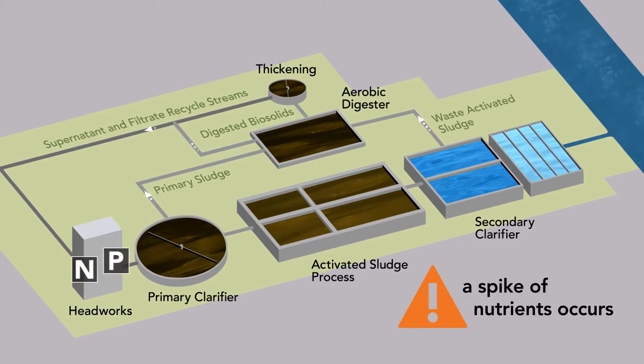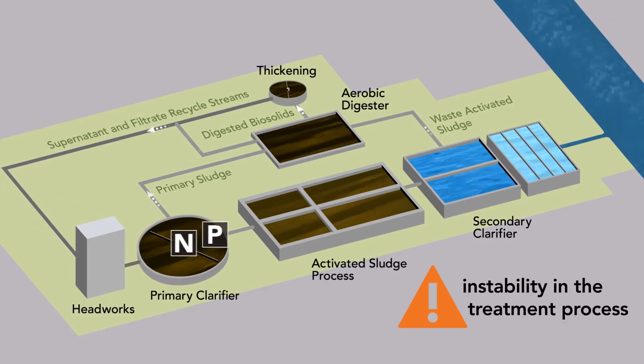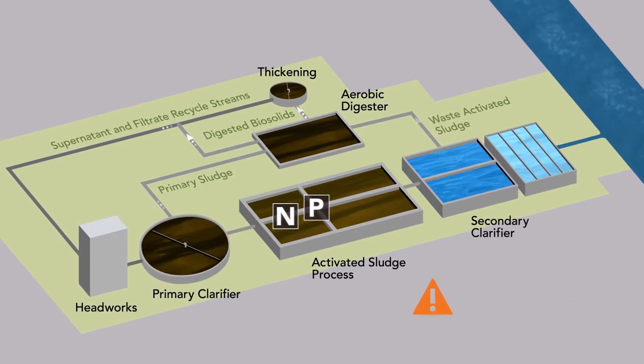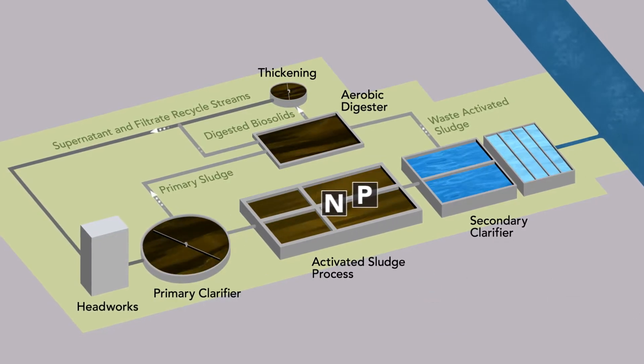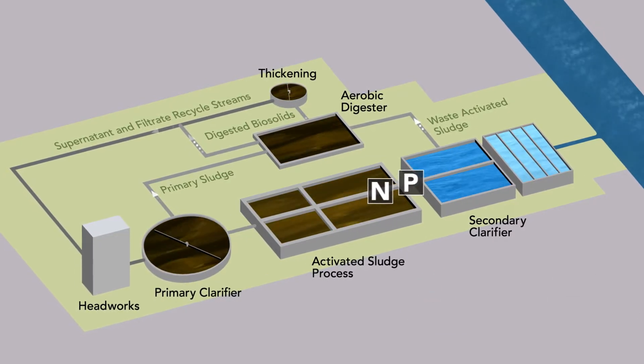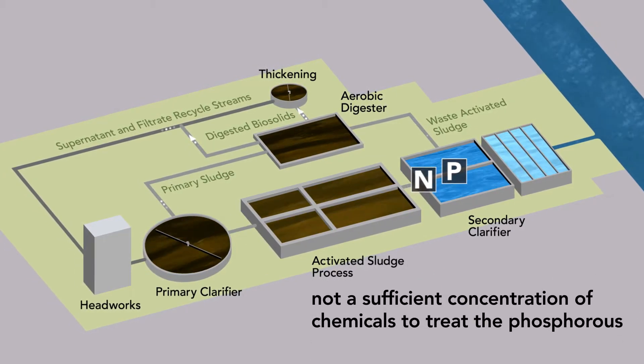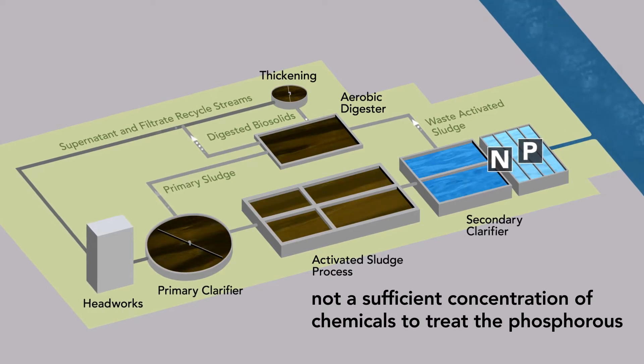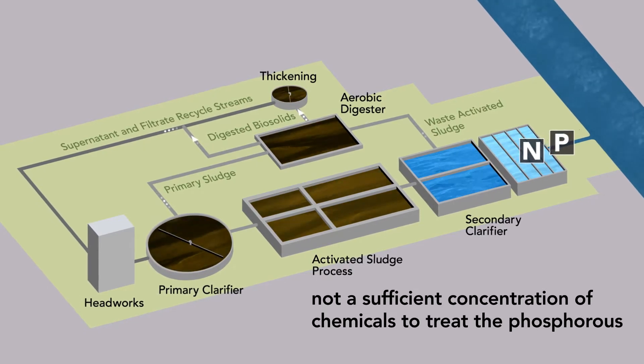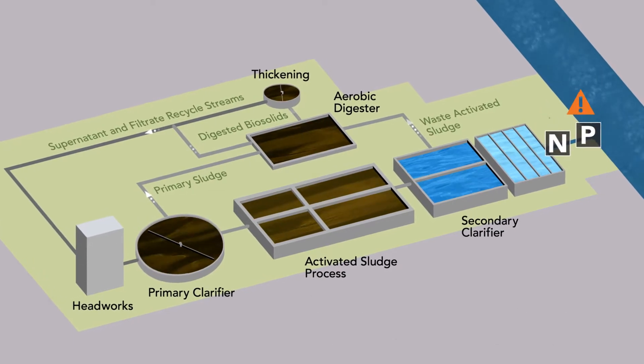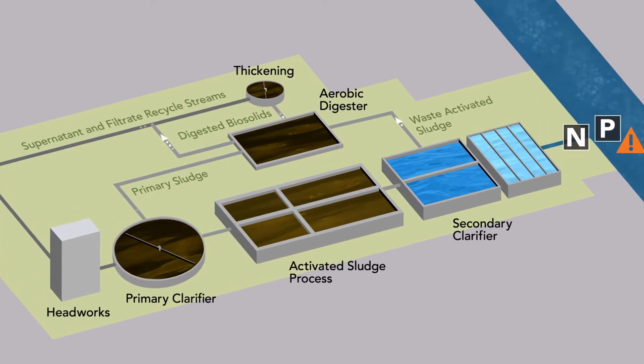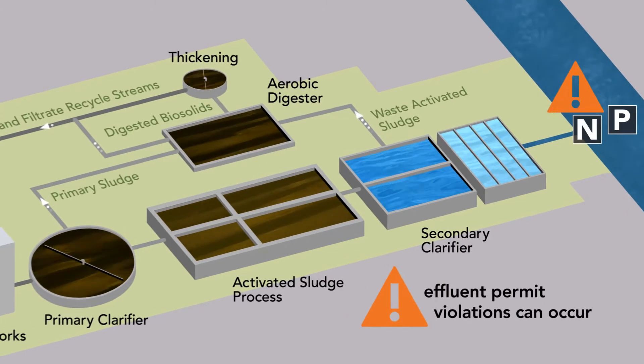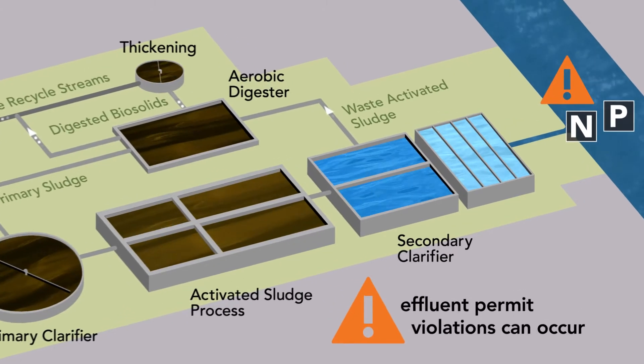This spike causes instability in the main treatment process because the biology is not acclimated to the load, or there is not a sufficient concentration of chemicals to treat the phosphorus. If the spike of nutrients is not effectively processed, effluent permit violations can occur.